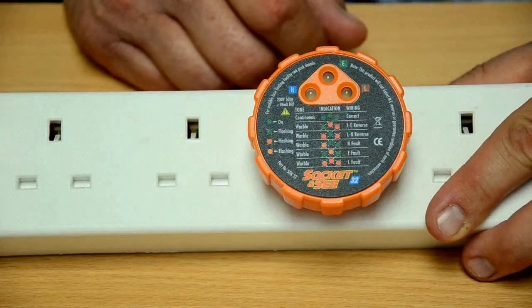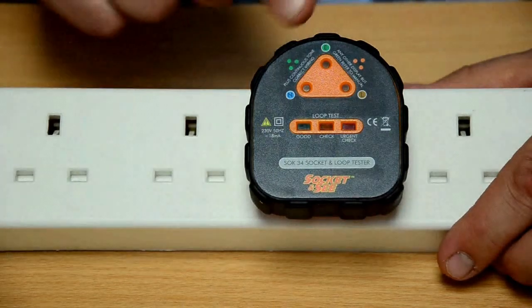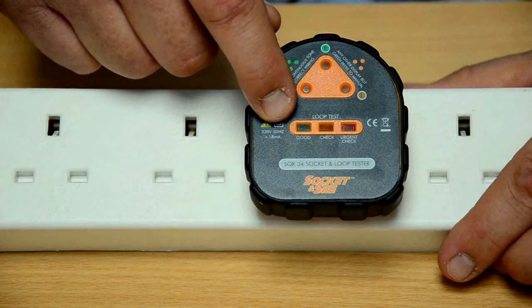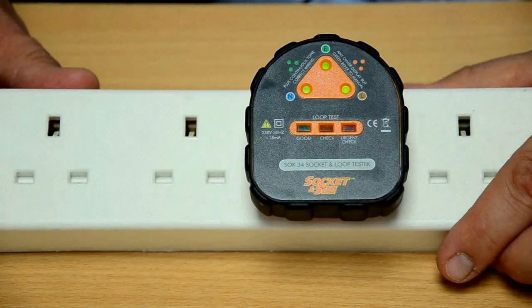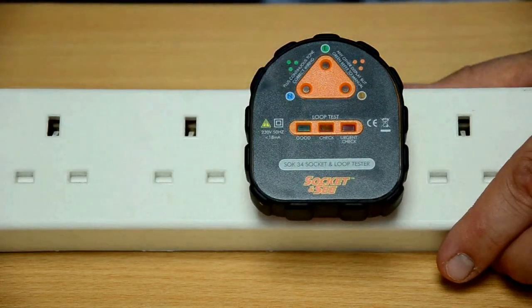So those were the simple socket testers. Now we're going to take a look at advanced socket testers, SOK34 and SOK36. Here we have the SOK34 advanced socket tester. Like the SOK32, it has the socket indication here and a row of LEDs here indicating the earth fault loop impedance. It should light green if it's good. In this case, the earth fault loop impedance is good.